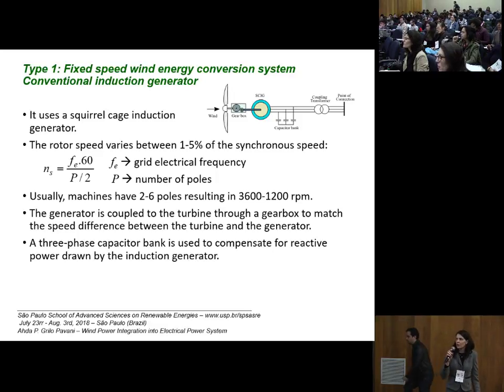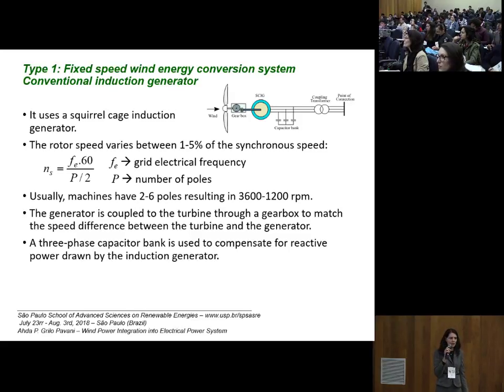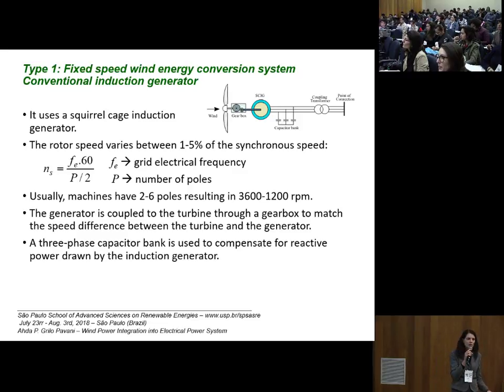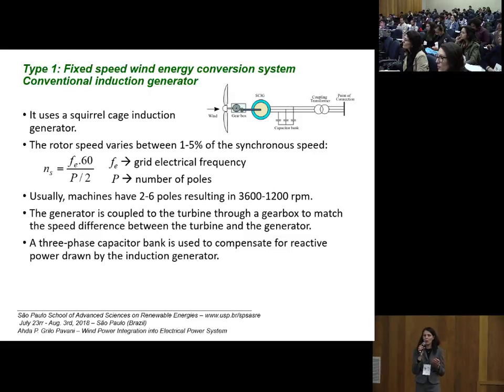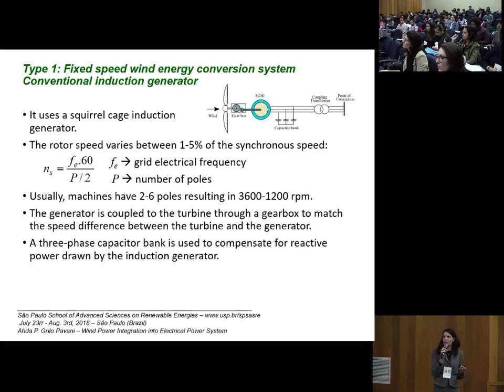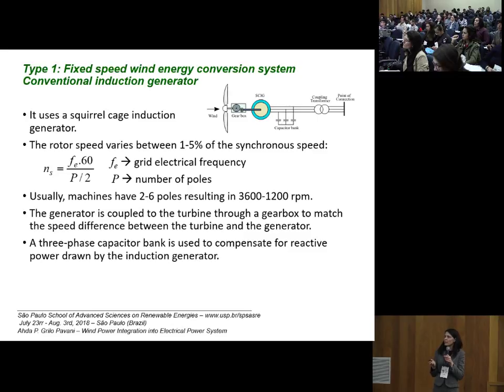The first type of wind energy conversion system is the fixed speed. It uses a conventional squirrel cage induction generator to convert mechanical energy to electrical energy. The rotor speed of a squirrel cage induction generator typically varies between 1% to 5% of the synchronous speed.